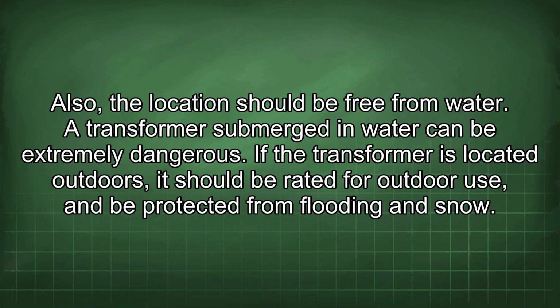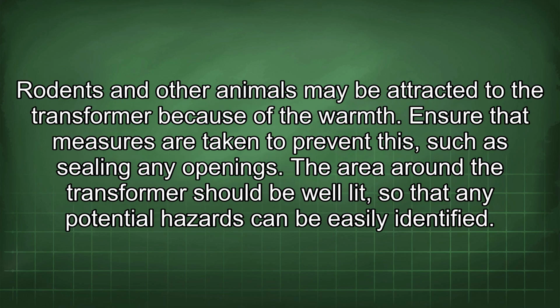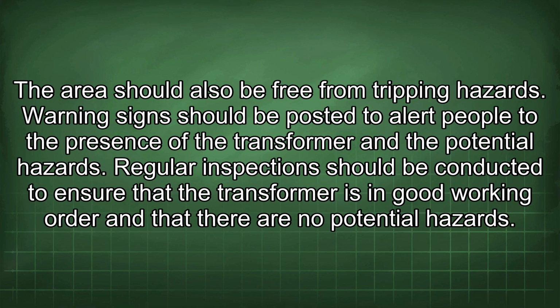If the transformer is located outdoors, it should be rated for outdoor use and be protected from flooding and snow. Rodents and other animals may be attracted to the transformer because of the warmth. Ensure that measures are taken to prevent this, such as sealing any opening. The area around the transformer should be well lit so that any potential hazards can be easily identified. The area should also be free from tripping hazards. Warning signs should be posted to alert people to the presence of the transformer and the potential hazards.